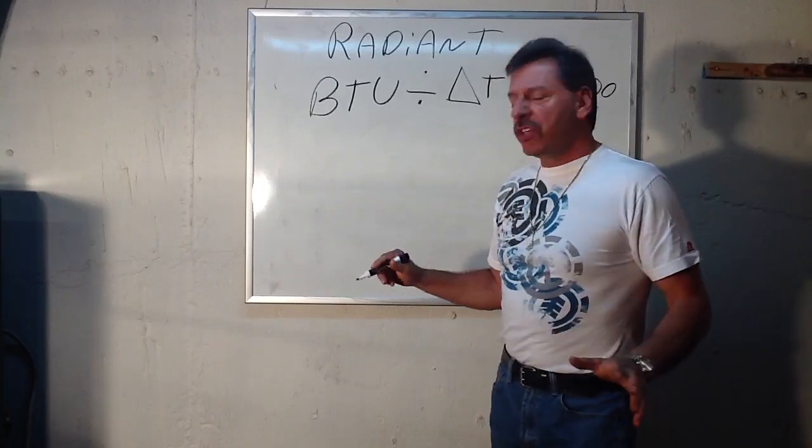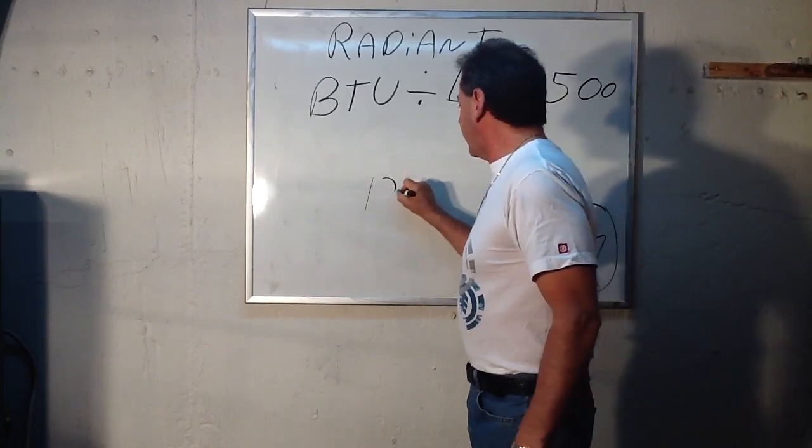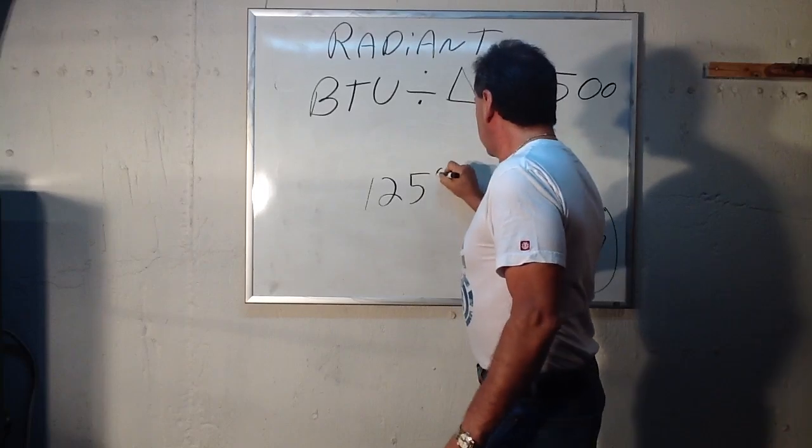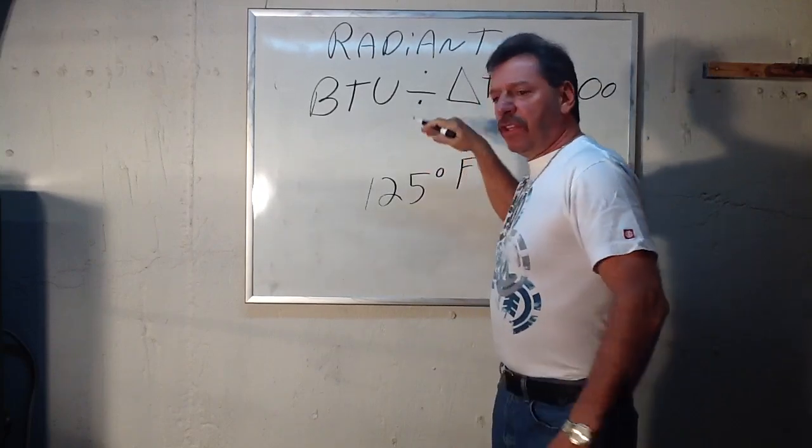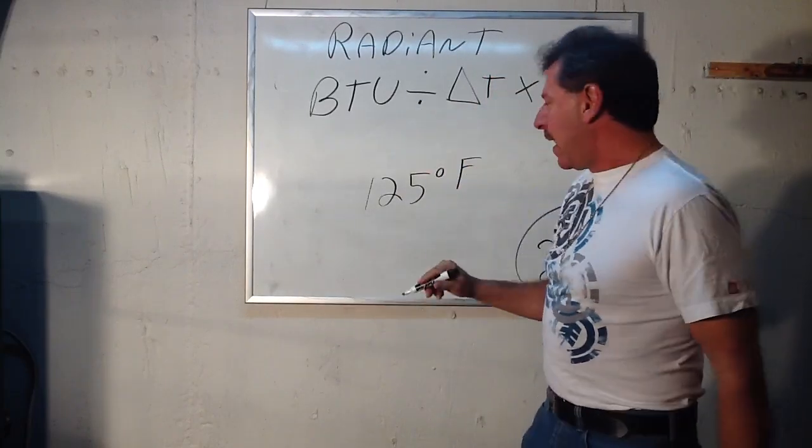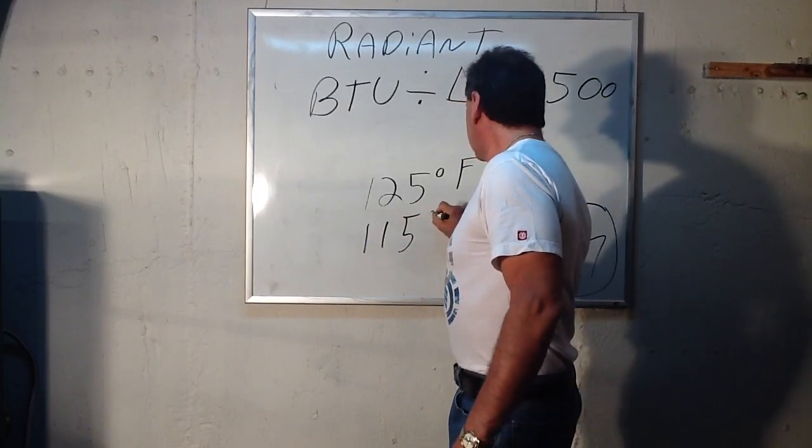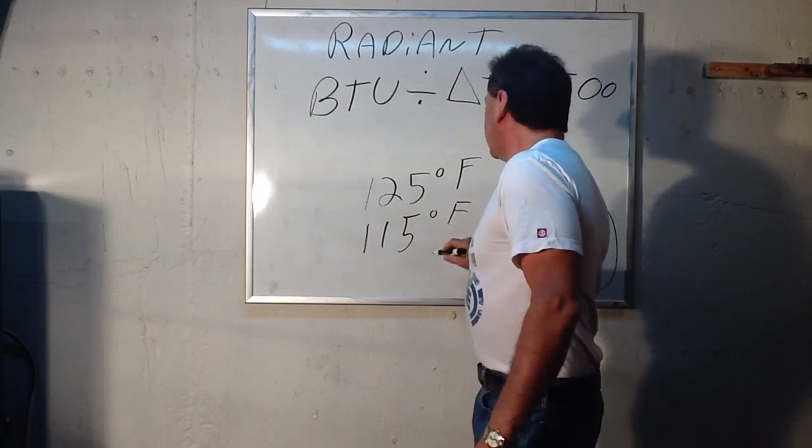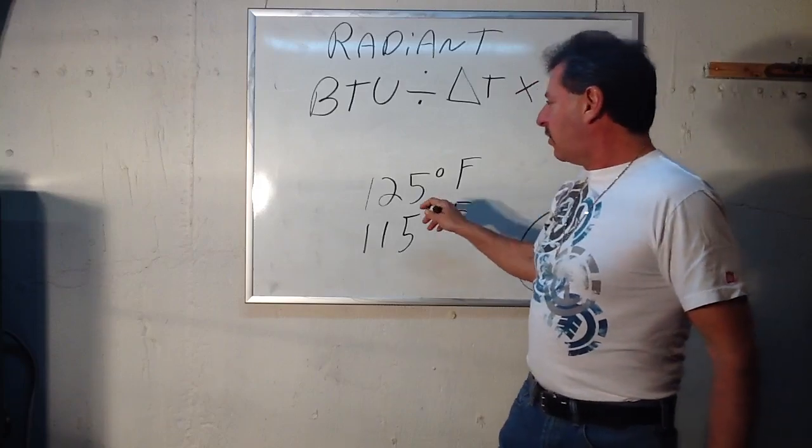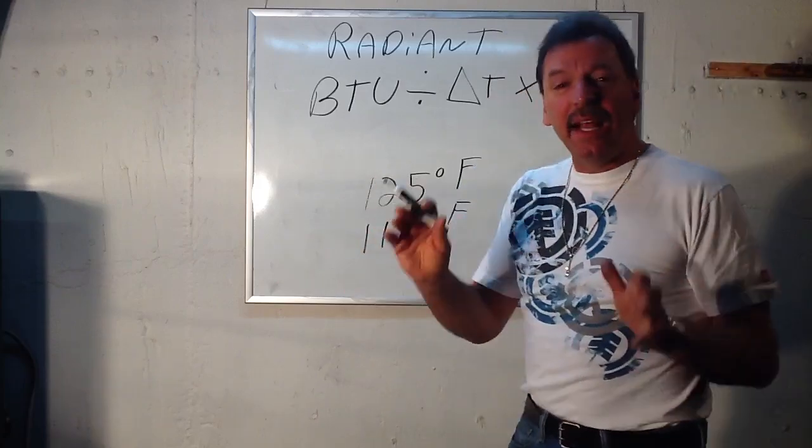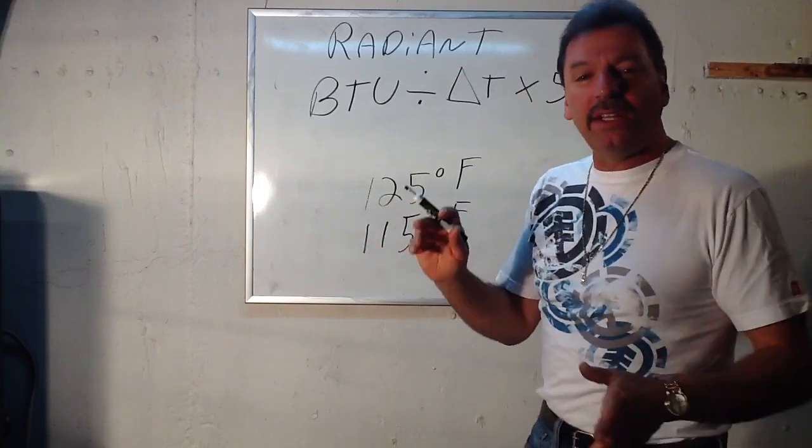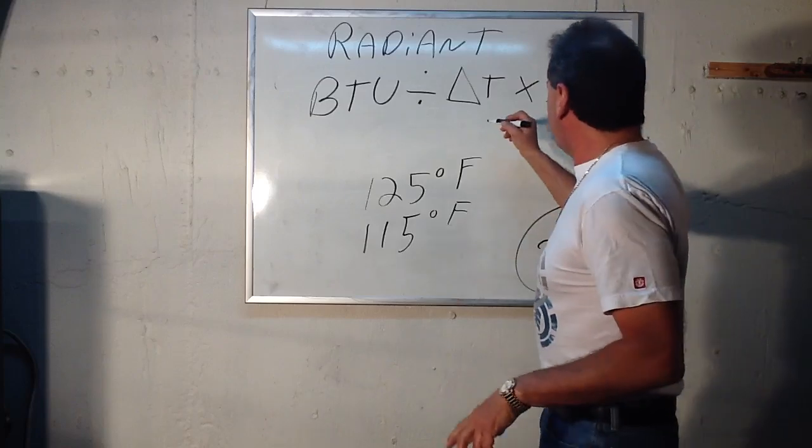Radiant heat leaves at about 125 degrees Fahrenheit and returns to the boiler at about 115 degrees Fahrenheit, so there's a 10 degree Delta T, or a 10 degree difference there. So your Delta T on radiant heat would be 10 instead of 20.